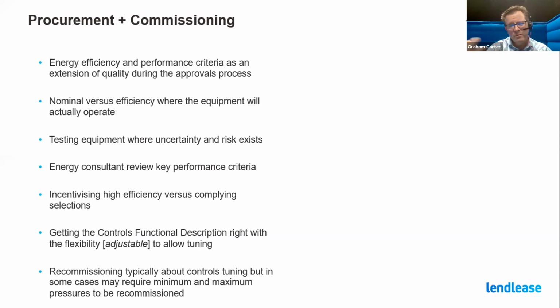When dealing with bigger equipment and plant, you have nominal efficiency, but also think about efficiency where the equipment will actually operate, and try to specify around that. It may not be the highest design point efficiency, but it'll be the best efficiency for where the building is likely to operate.